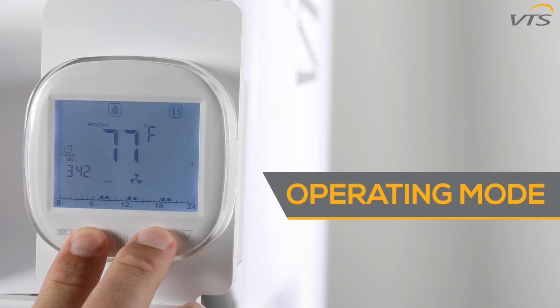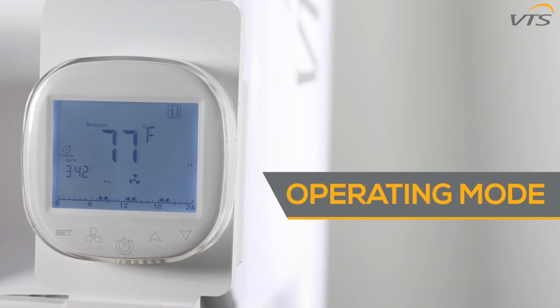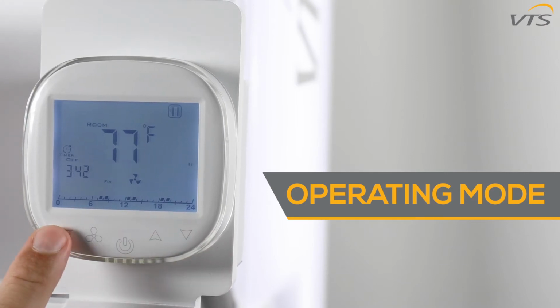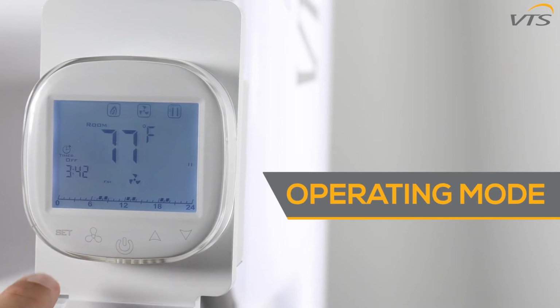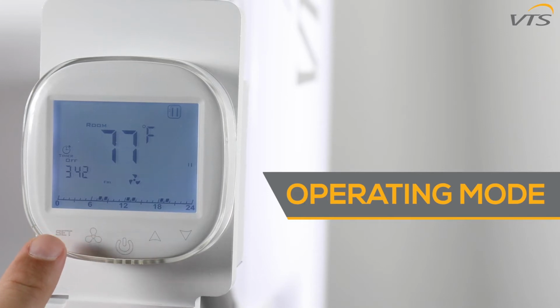To change the operating mode, hold down the fan button and up button simultaneously. You can scroll between modes by hitting the set button. Your options are heating, ventilation, and heating plus ventilation. The operating mode options you have are determined by your advanced settings. We'll discuss advanced settings in a bit.